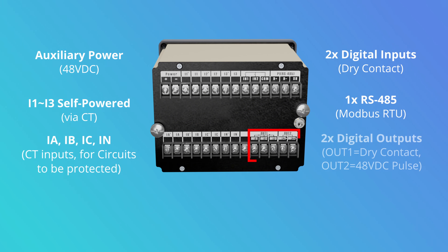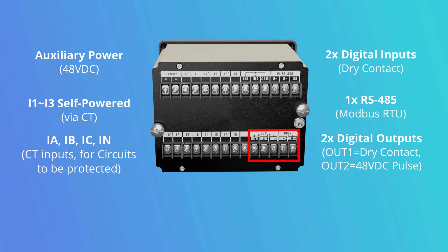Lastly, there are two digital output ports. OUT1 is a dry contact DO with either normally open or normally closed circuit, normally used for alarm signals, etc. OUT2 is a port for active pulse output used for tripping your breaker, which you need to make sure matches your trip coil voltage.